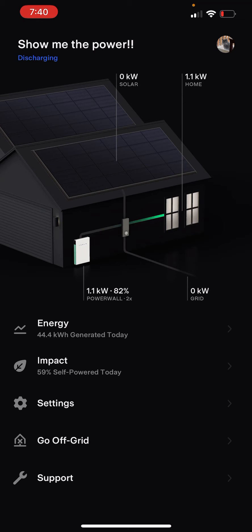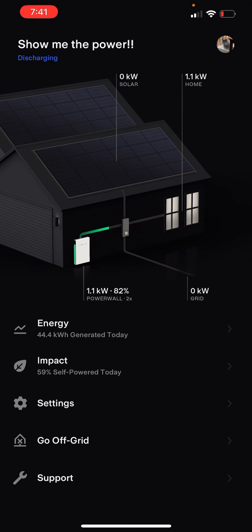You'll see it's still using about 1.1 kilowatts just after your AC finishes running the compressor. The fan will keep running so that it keeps air going across the coils — you need that airflow so the coils don't freeze up. So even after your condenser has finished running, the fan will keep blowing air over that coil until those coils thaw out.